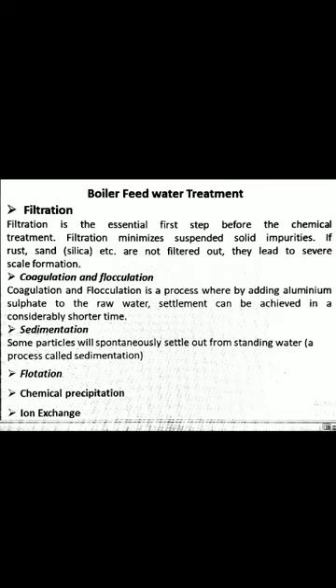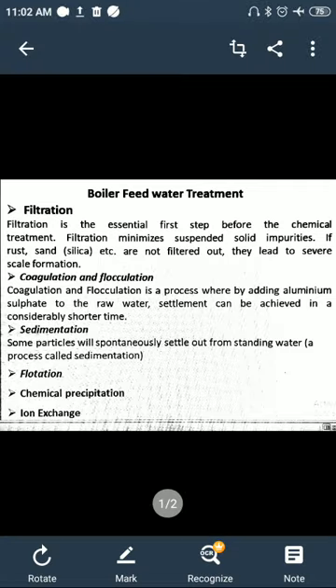Next is flotation. The natural flotation process differs from flotation with air. In the first case, material particles lighter than water — oils or greases eventually associated with gas bubbles — have the tendency to rise to the stationary liquid surface. In the flotation process with air, material particles heavier than water are transported to the liquid surface by attaching them with air bubbles. It is a process for removing suspended particles from liquid by bringing particles to the surface. The influent feed liquid can be raw water, wastewater, or liquid sludge.